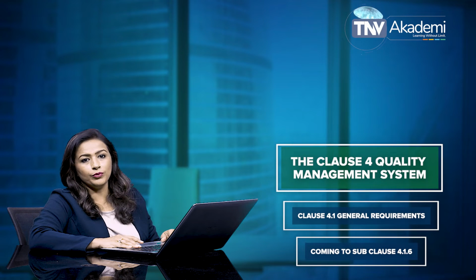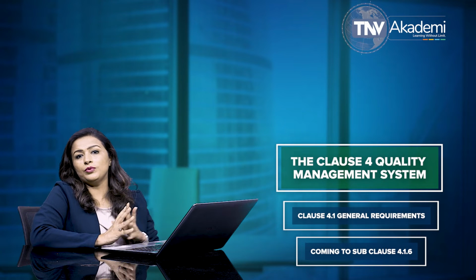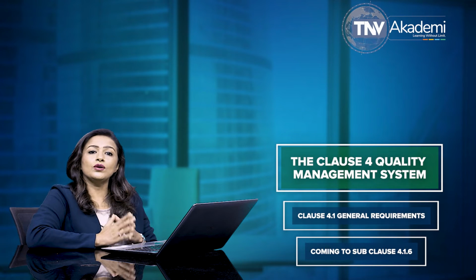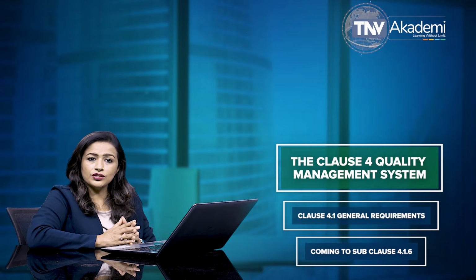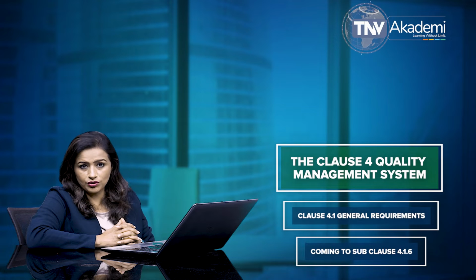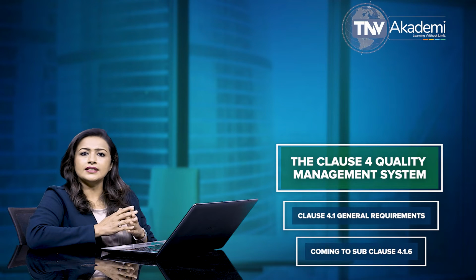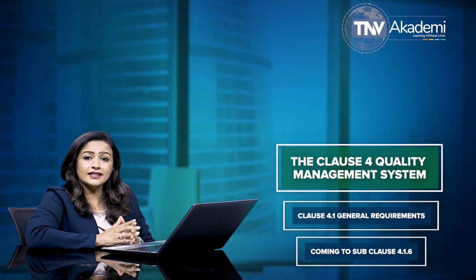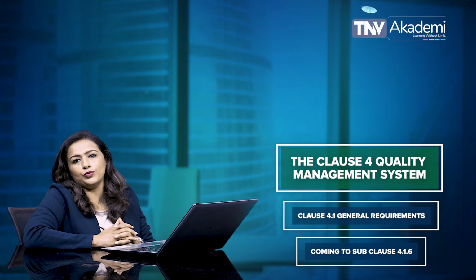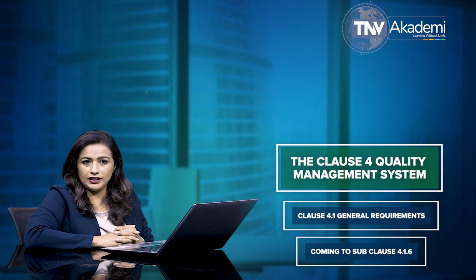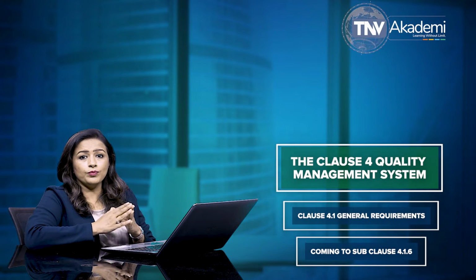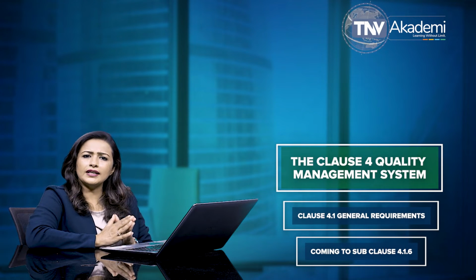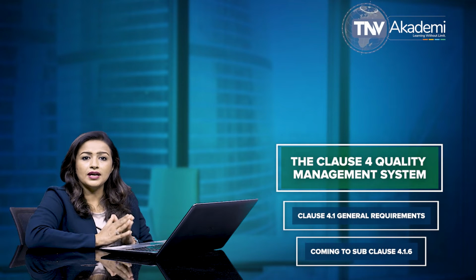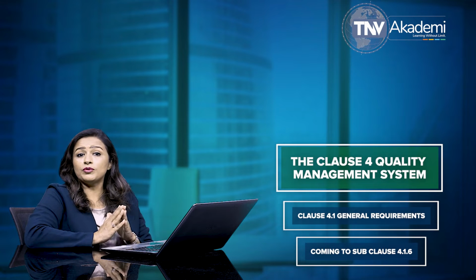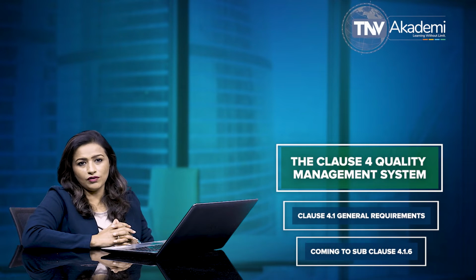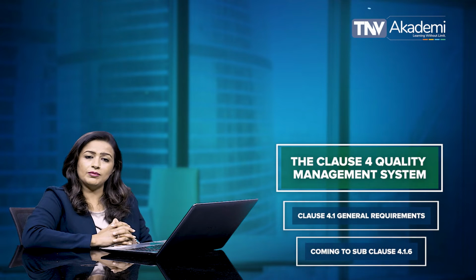Coming to subclause 4.1.6. The subclause 4.1.6 of the standard specifies that the organization is required to document procedures for the validation of the application of computer software used in the quality management system. Such software applications are required to be validated prior to initial use and, as appropriate, after changes to such software or its application. As per this clause 4.1.6, the specific approach and activities associated with software validation and revalidation are required to be proportionate to the risk associated with the use of the software. Records of such activities shall be maintained.